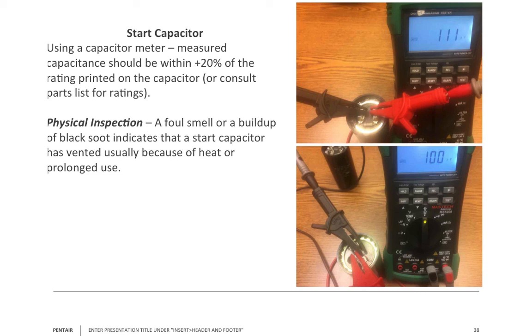Here's our start capacitor. Remember, best thing is first physically inspect it. Make sure that it's not damaged. You might see the dielectric material leaking out, then we know it's damaged. If not, hook it up.